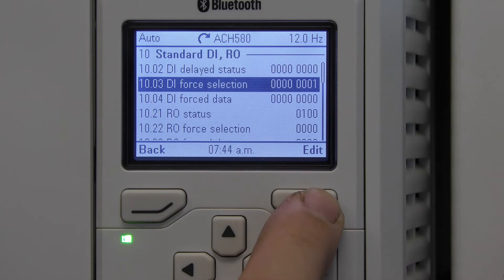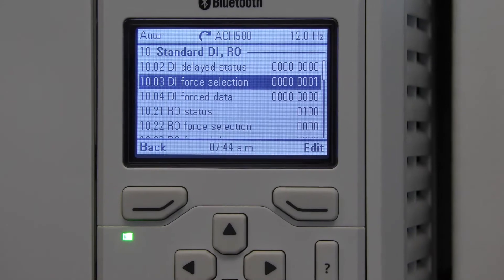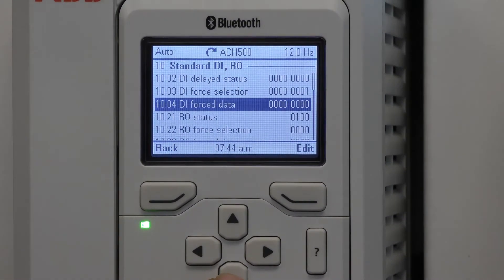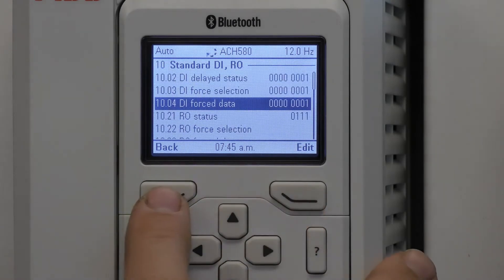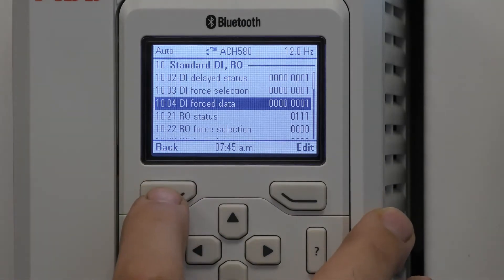Now in order for this to take effect I have to change the parameter in 10.04 DI forced data to a one also. Save. As soon as I do that you'll notice that the drive is coming on and I did not actually energize a digital input — I did it through the software of the drive.